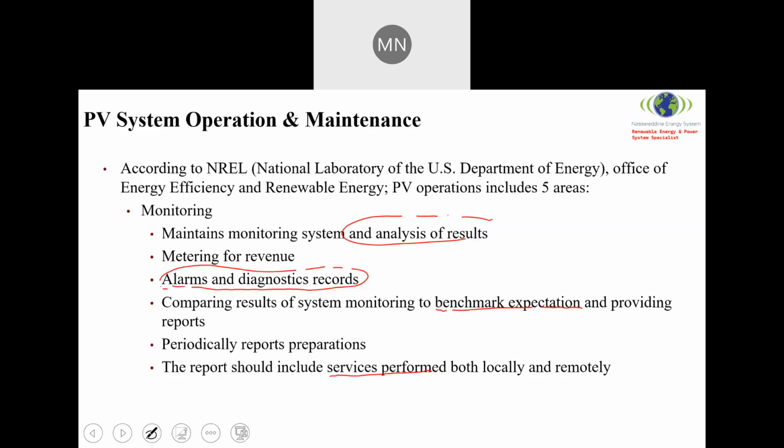Maybe the part that you changed is not suitable. Maybe by mistake your inventory division brought you a lesser, for example, maximum power point tracker. If you need 200 amps, by mistake maybe they got you 150 or 100. So you need to include this in the report so your engineer, your assessor, will be able to determine if it's on the right track or if it's not on the right track.